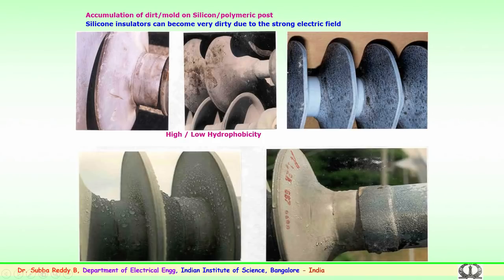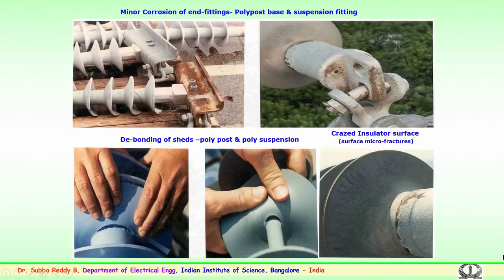Now, a lot of technology improvements have happened in the material aspects and also in the manufacturing processes. Here you see the corrosion of the end fittings. This could lead to failures of post insulators or suspension type insulators. Similarly, the debonding of the sheds: if it is not properly taken care of during the manufacturing period, this debonding of the sheds could lead to failures over a period of time.